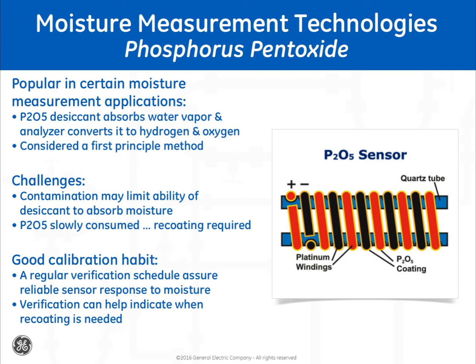Since the P2O5 desiccant isn't a perfect desiccant, a regular verification schedule will provide indication of when the imperfection impacts the accuracy of the analyzer. One can use calibration cylinders or a portable analyzer to ensure that the real-world sensor and measurement system behave as physics would dictate.